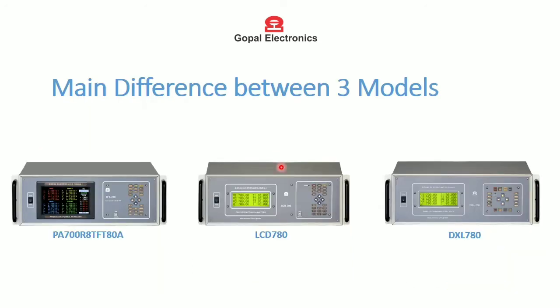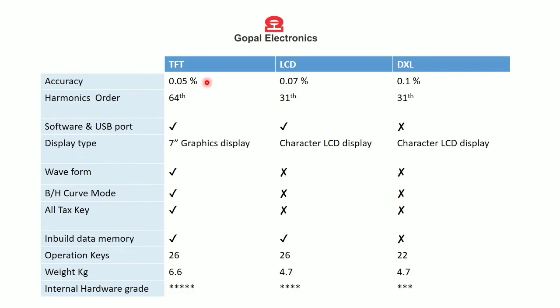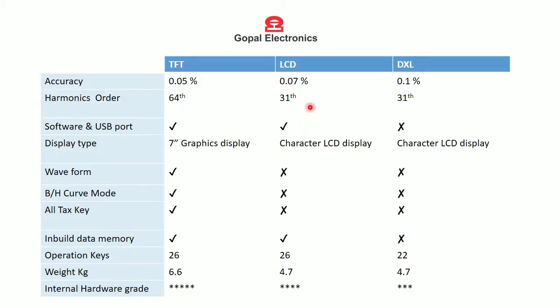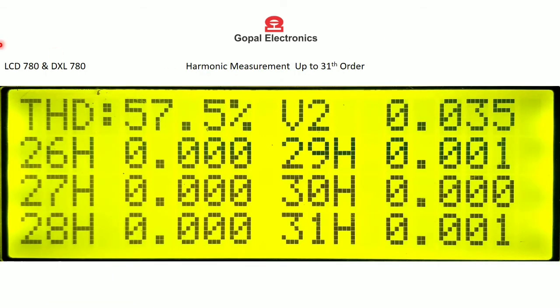The main differences between all three models: accuracy of the TFT model is 0.05%, accuracy of the LCD model is 0.07%, and accuracy of the DXL model is 0.1%. The TFT model can measure harmonics up to the 64th order, whereas the LCD and DXL models can measure harmonics up to the 31st order.